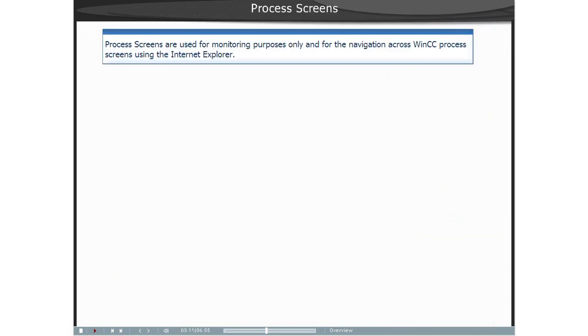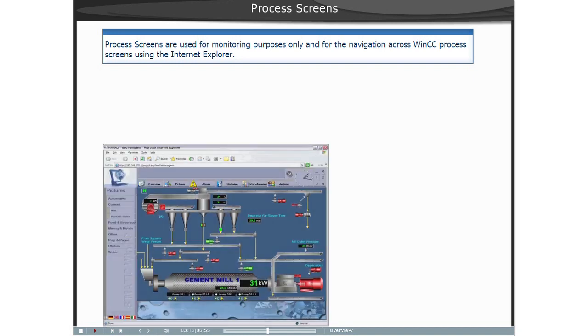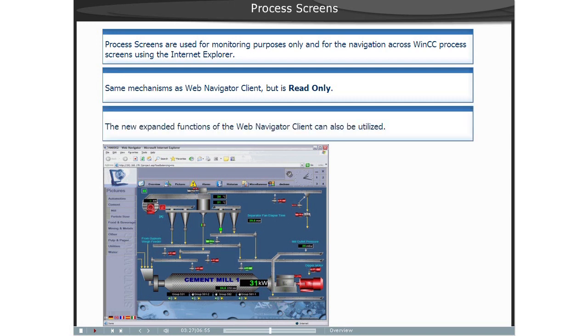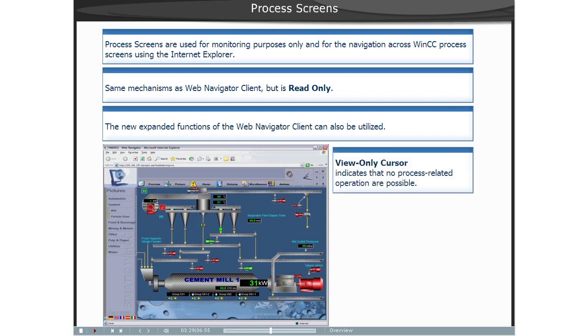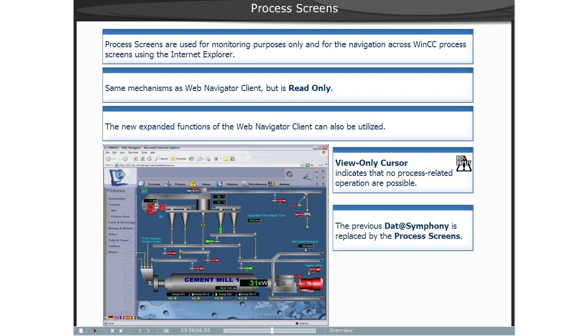The function Process Screens of Data Monitor serves exclusively to monitor and navigate via the WinCC Process Screens with the Microsoft Internet Explorer as a read-only client. Only the process screens published using Web Publisher of WinCC Web Navigator are displayed. The cursor displayed is a read-only cursor, indicating to the user that the process-related operations are not allowed.